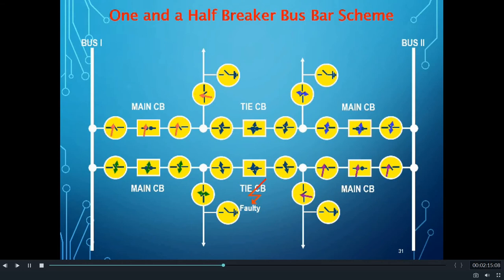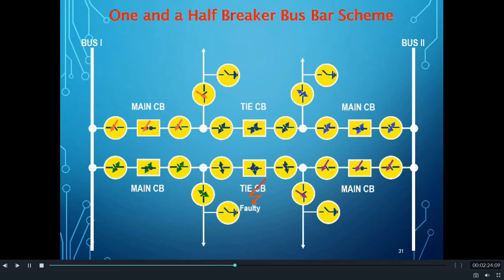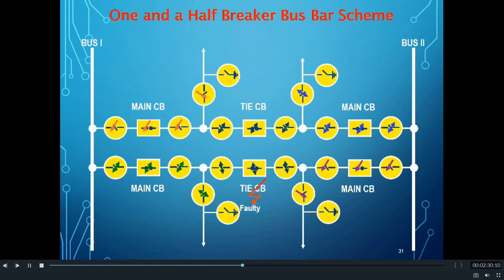Because of this fault, the tie CB trips and the isolators across the tie CB are opened manually. However, it can be clearly seen that because of the fault in the tie CB, none of the bays connected to it are affected. Both feeders remain connected to either of the busbars through the main circuit breakers.